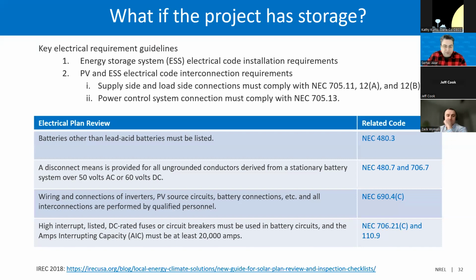Power control systems must comply with National Electrical Code 705.13. And batteries other than lead acid batteries must be listed. A disconnect means is provided for all ungrounded conductors derived from a stationary battery system over 50 volts AC or 60 volts DC. Wiring connections of PV inverters, PV source circuits, battery connections, and all interconnections are performed by qualified personnel. And high interrupt listed DC rated fuses or circuit breakers must be used in battery circuits, and the amps interrupting capacity (AIC) must be at least 20,000 amps.